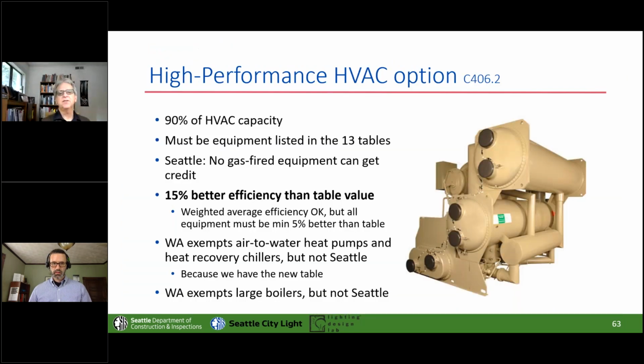Instead of DOAS, you can do this—this one's your C406.2. You can get at least 90% of your HVAC capacity from equipment in those tables if it's not gas. Actually, it's 15%, not 10—you've got to be 15% better than the table value.